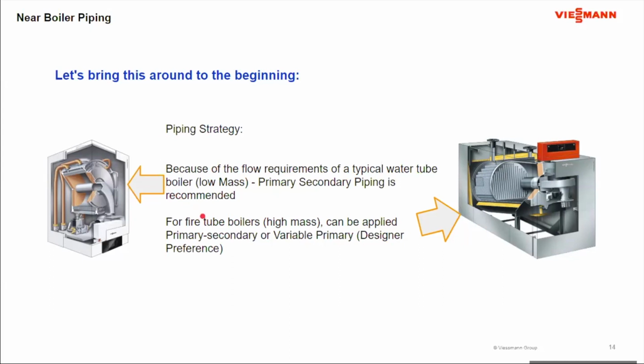However, for fire tube boilers, because they have that higher mass, they have lower heat flux, and the mass allows everything to work with each other, even though the control is responding at a slower rate. When I do a higher mass boiler, I don't necessarily have to do primary, secondary. I can do variable primary as well. So really, with this style of boiler, this becomes the designing engineer's call on which way to go. Do I want to go primary, secondary? Do I want to go variable primary? Okay.